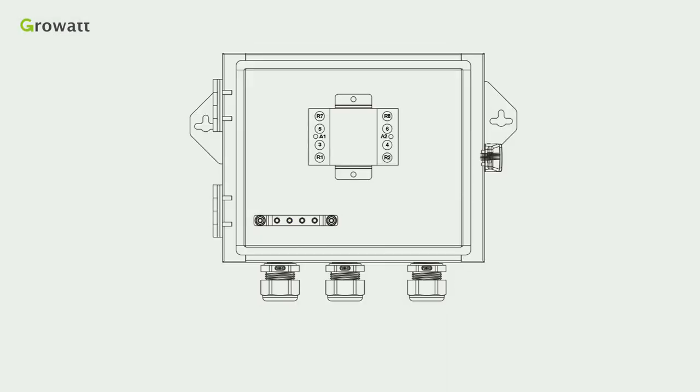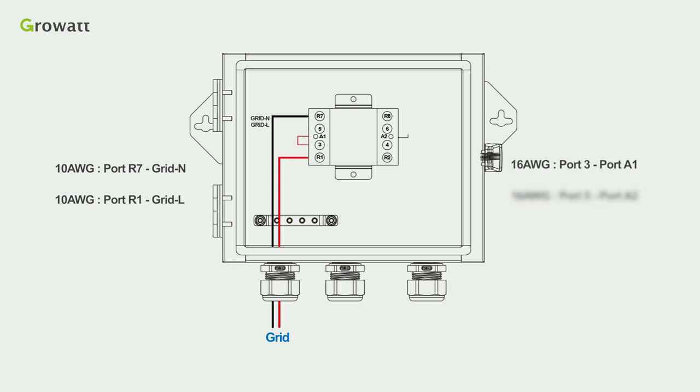Firstly, for grid connection: Use the 10 AWG cables to connect the port R7 from the N line of the grid and connect the port R1 from the L line of the grid. Use one 16 AWG cable to connect the port 3, port A1 and the other 16 AWG cable to connect the port 5, port A2. Connect the grounding cable finally.